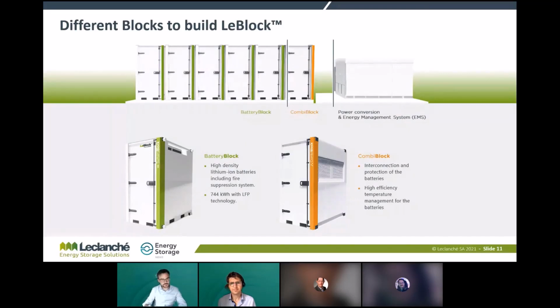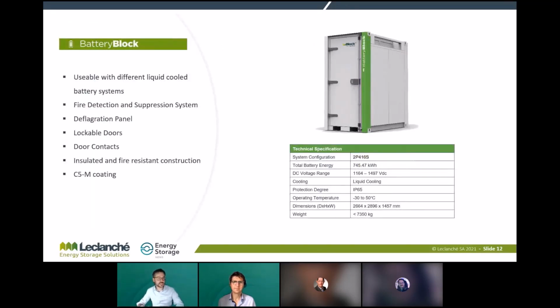The battery block, as you can see on the next slide, uses LFP cells, has values up to roughly 745 kilowatt hours, and contains a liquid cooled battery. Each battery block is equipped with automatic fire detection and suppression, deflagration panels on top, and lockable, monitored doors on both sides.